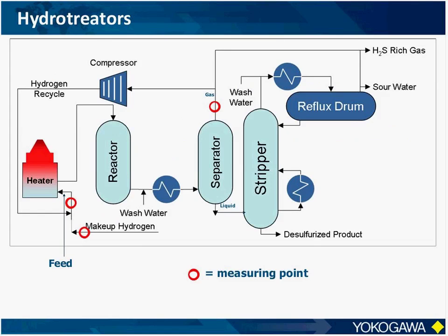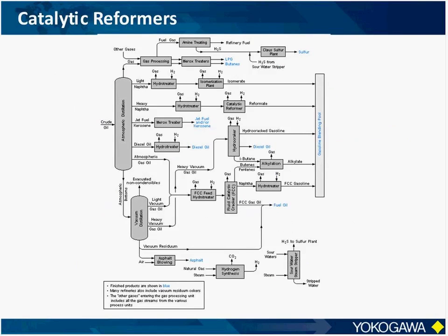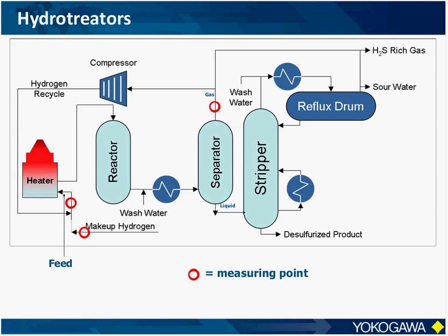Now, the simplified layout shows the hydrotreating process and points where specific gravity or hydrogen purity can be measured to improve the efficiency of the process and to reduce the hydrogen consumption. The gas coming off the separator can be measured to indicate hydrogen content. This will determine how much makeup hydrogen is required to increase the hydrogen concentration to a required level to recycle it back to the process. And the makeup hydrogen can be monitored as well to confirm its purity.